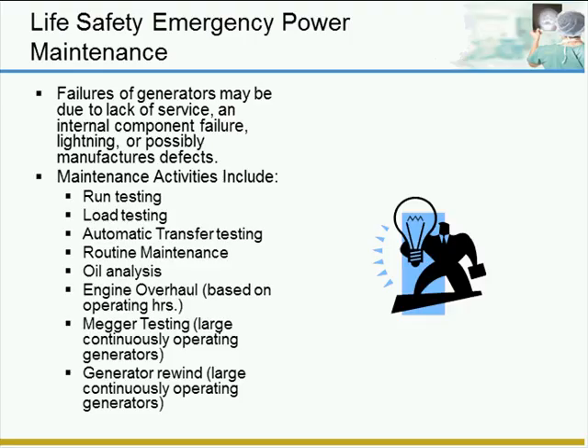A little bit of maintenance on your generators. Your generators should be run tested weekly, monthly if weekly is not possible. Load tests should be done annually to make sure that the unit will operate normally if it was to be called into service. Routine maintenance should include the cleaning of the air filters and fuel filters, monitoring all system levels, the coolant, oil, things of that nature. OEM guidelines will really illustrate the oil specifications and oil analysis. Oil analysis should be done annually to determine the internal operating conditions of the unit.